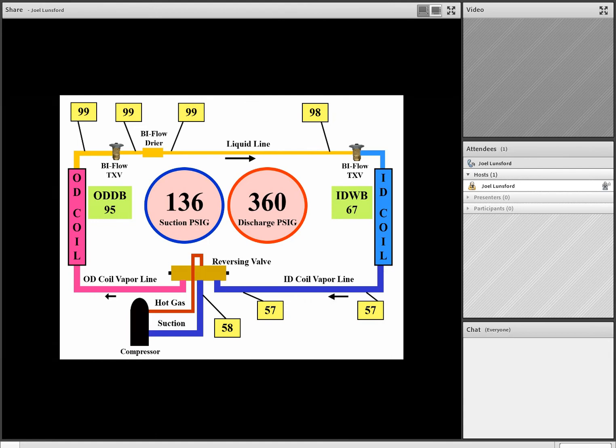As we take a look at the temperatures throughout the refrigeration circuit, we see that there's no significant temperature difference across key components in the refrigeration circuit. Pressures are normal. Superheat is normal. Subcooling is normal. This is a normal service call. And team, this is important that we recognize normal as well when we're doing diagnostics. We need to be able to recognize normal as well.